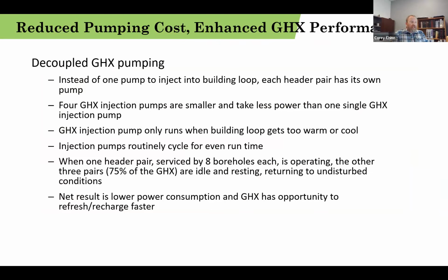All right. Decouple your ground heat exchanger piping. We really enjoyed this individual header pair injection system. We allow three of the loops to rest a lot of the time, and one loop is carrying the load. So it's kind of fun. We get really good temperatures off of it. We operate very efficiently. Many times we're in this building and actually none of the injection loop pumps are running because they're not needing additional load.